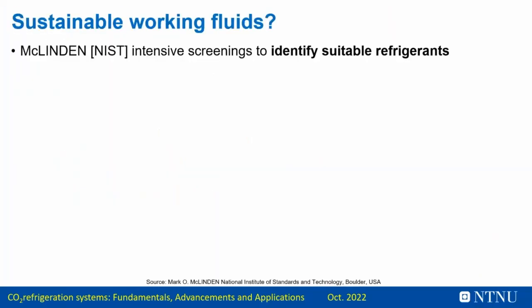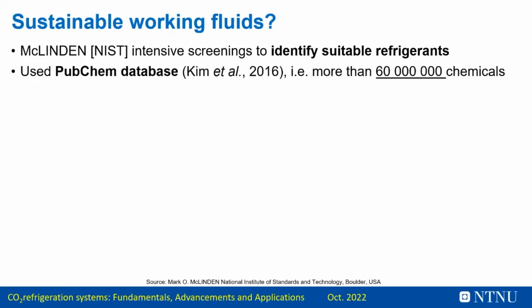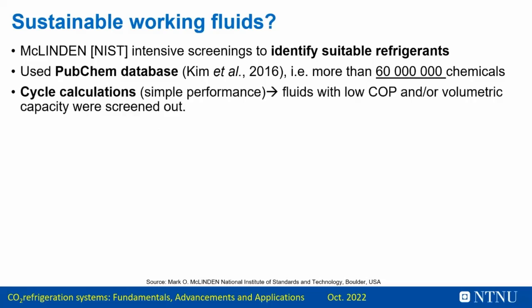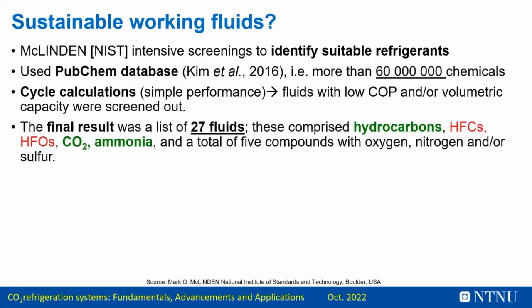What are sustainable working fluids? McLinden from NIST in the US intensively screened to identify these fluids. He used the PubChem database, and he analyzed more than 60 million chemical combinations. He did some simple cycle calculations to investigate the performance of these fluids in a system, in terms of COP and volumetric capacity. That is what he screened on 60 million combinations. And the final result was a list of 27 fluids, which you can find in his publication. And these comprise hydrocarbons, some HFCs, some HFOs, short-life HFCs actually, CO2, ammonia, and a total of 5 components with oxygen, nitrogen, or sulfur.